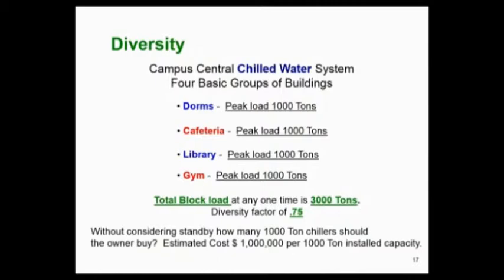It's a real simple concept, and let's say we've got a central chill water plant with a dorm with a thousand ton load, cafeteria with a thousand ton, library with a thousand ton, and a gym. So if you add up the individual loads, it's 4,000 tons. But if you ran a block load, look at all those four buildings at any one time, and the peak block load of those four buildings is 3,000 tons. Now by my definition, that's a diversity factor of 0.75.